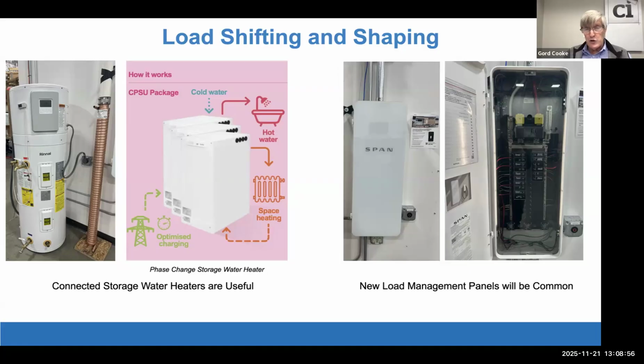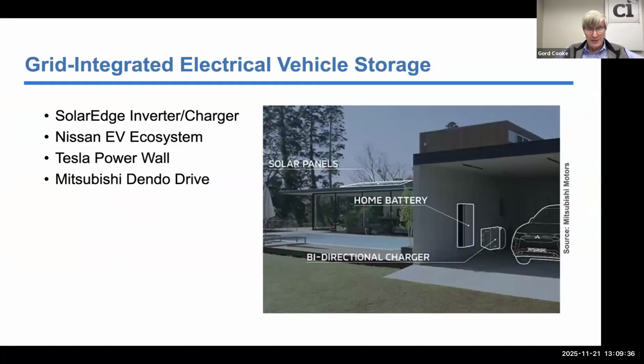On the right-hand side, a profusion of panels now coming. This is a particular manufacturer, Span, who's able to manage loads and is able to say dryer and air conditioner shouldn't run at the same time. EV and dryer don't need to be on at the same time. So on a breaker by breaker basis, it can rationalize that out. And we're finding large builders are able to use this in their communities to avoid oversizing transformers, and utilities are working closely with them to say, if we have a constraint in a particular neighborhood, we can use these kinds of strategies to reduce the panel sizes and therefore the transformer sizes. Indeed, a couple of examples of using solar panels and a bidirectional charger and a home battery to flatten out the peaks in this house and show that it can stay within 100 amps.